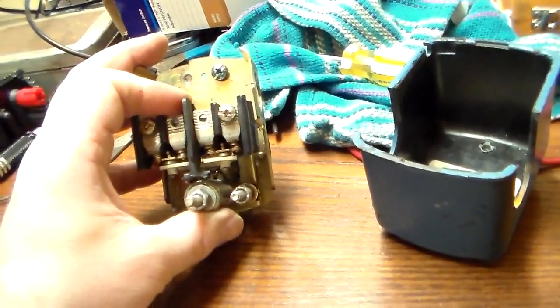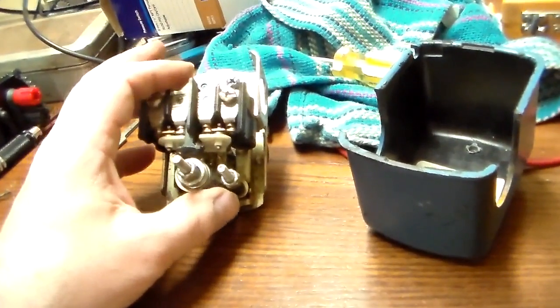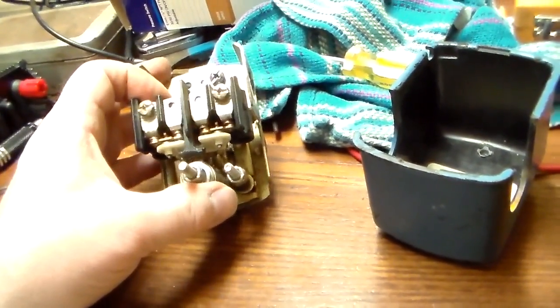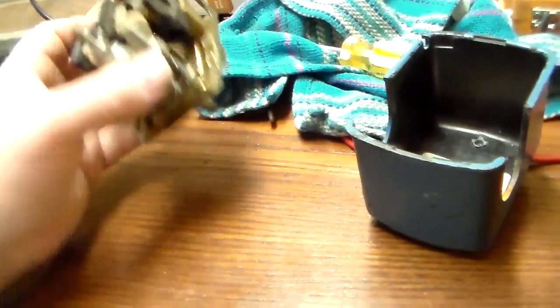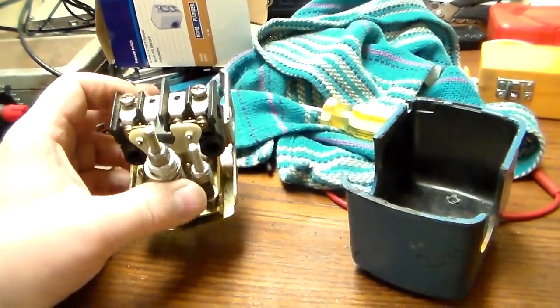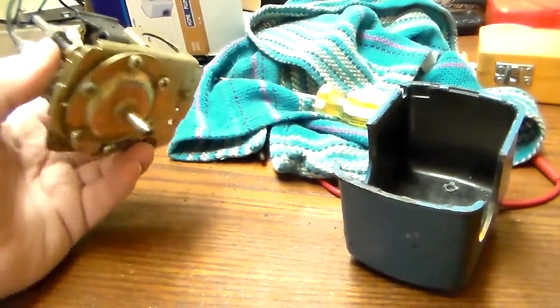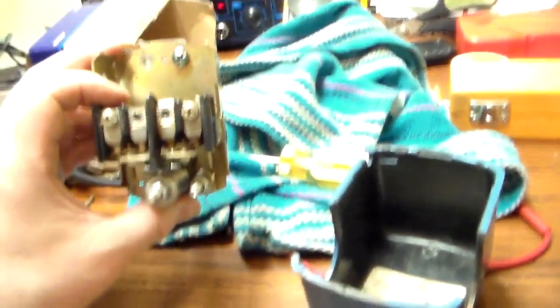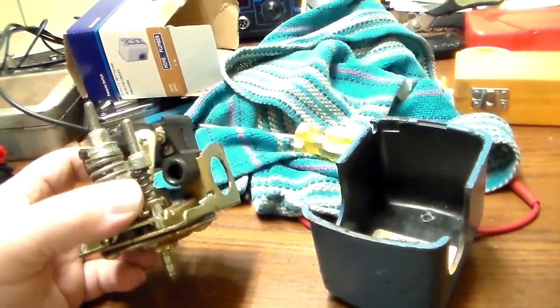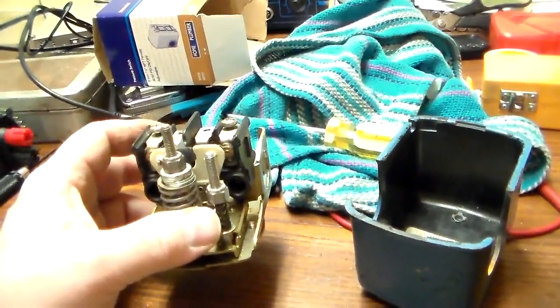If you push any higher than 50 psi on a jet pump you're going to be burning the things out or it's going to be running continuously and very rarely being able to get up to pressure anything past 50. 50 has always been good for jet pumps. If you have a submersible pump I like to set mine at about 60 to cut out and 50 to cut in. That way there's not as much noticeable difference. Even with the jet pumps, if you got the patience to sit there and cycle it and cycle it and adjust the differential to try to get it closer to a 10 psi differential as opposed to a 20, you know, to me 20 psi difference when you're at the pump, by the time you get to the end of your faucet runs and stuff like that, you're probably at 30 psi going to be down to around 20 psi by the time you get to the end of your run.